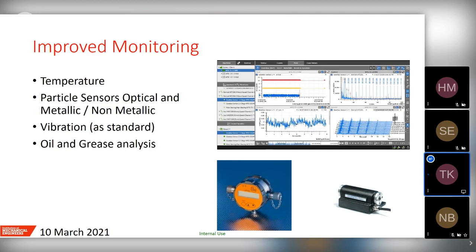Vibration is now fitted as standard. The first of them didn't have them. Then they realized how good it was, and they started retrofitting them. Now, of course, it's standard on such an expensive piece of kit. Those are now vastly more developed than they used to be, and they are highly reliable. But the problem now, as we said, is that you're going to get turbines running at only 7, 8 RPM. Trying to detect any damage at that lower RPM is very hard. It can be done, but it isn't as easy as you'd hope. Most vibration systems are running at much, much higher speeds.